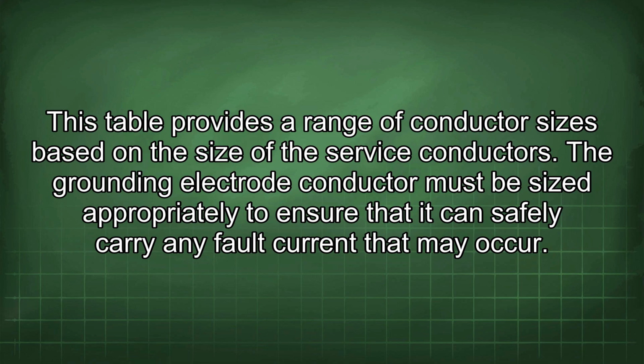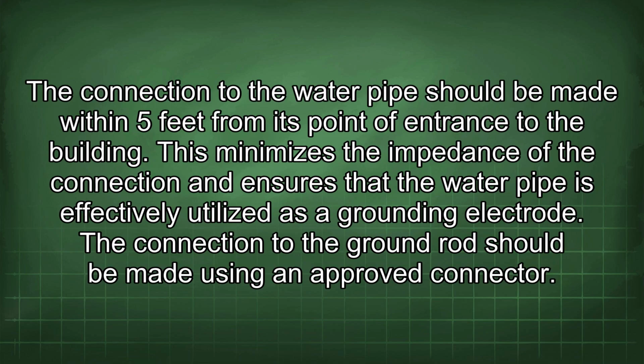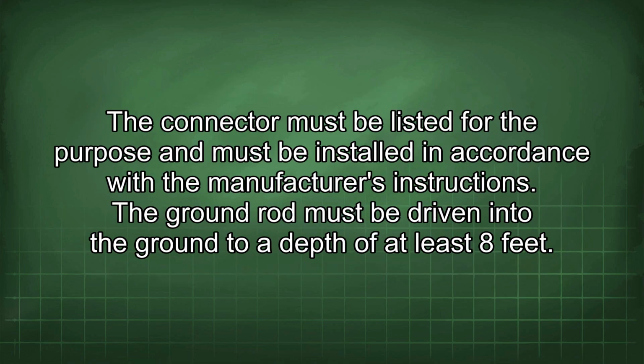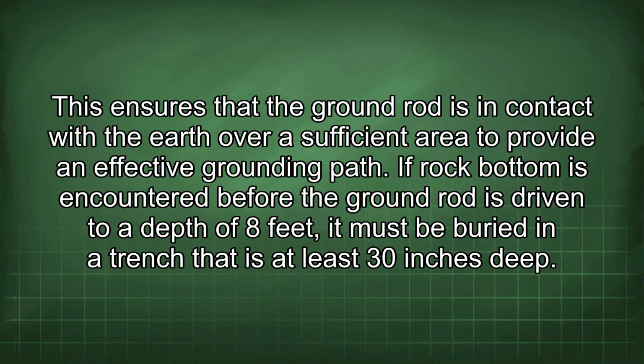The grounding electrode conductor must be sized appropriately to ensure that it can safely carry any fault current that may occur. The connection to the water pipe should be made within 5 feet from its point of entrance to the building. This minimizes the impedance of the connection and ensures that the water pipe is effectively utilized as a grounding electrode. The connection to the ground rod should be made using an approved connector. The connector must be listed for the purpose and must be installed in accordance with the manufacturer's instructions. The ground rod must be driven into the ground to a depth of at least 8 feet. This ensures that the ground rod is in contact with the earth over a sufficient area to provide an effective grounding path.